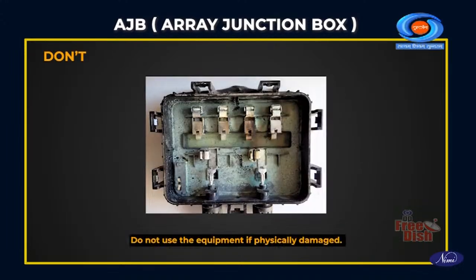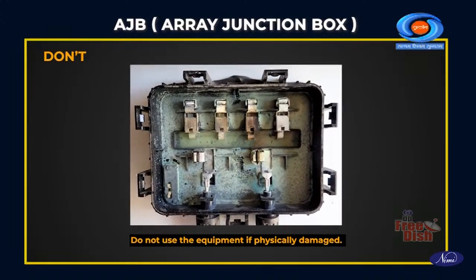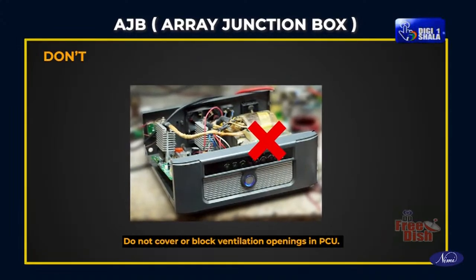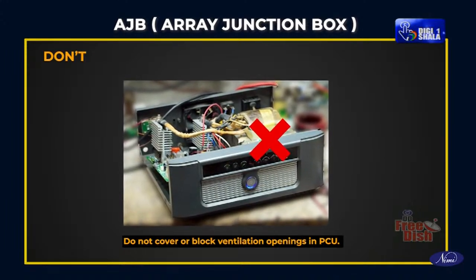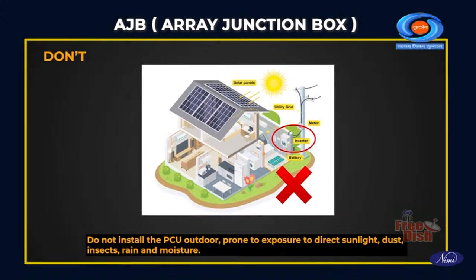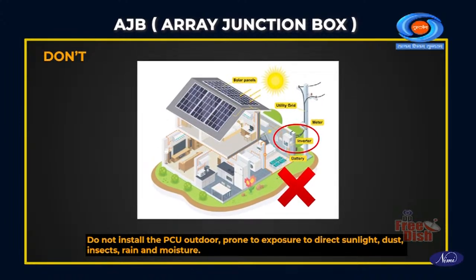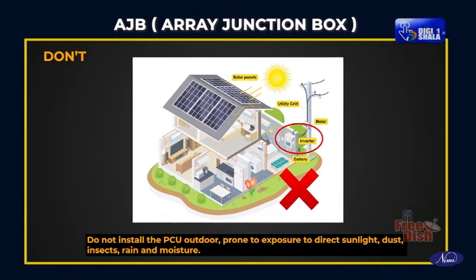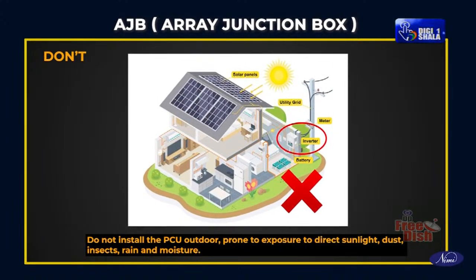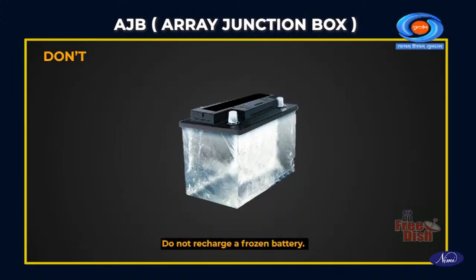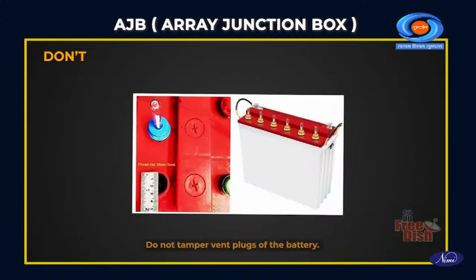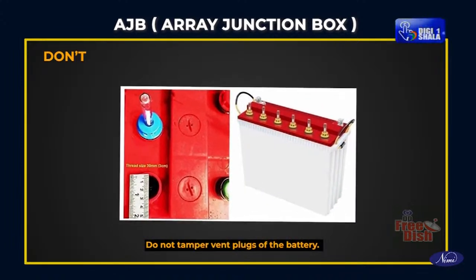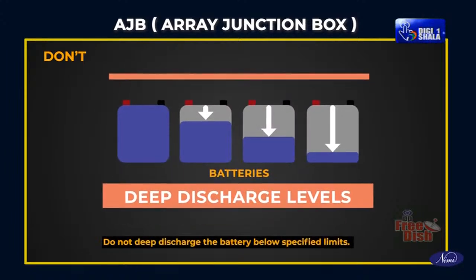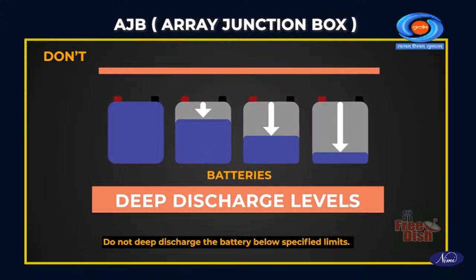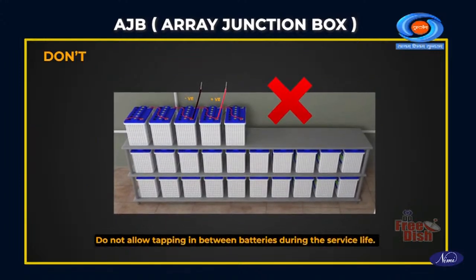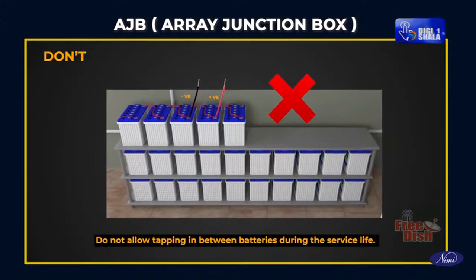Don'ts: Do not use the equipment if physically damaged. Do not cover or block ventilation openings in the PCU. Do not install the PCU outdoors, where it is exposed to direct sunlight, dust, insects, rain and moisture. Do not recharge a frozen battery. Do not tamper with the vent plugs of the battery. Do not deep discharge the battery below specified limits. Do not allow tapping in between batteries during the service life.